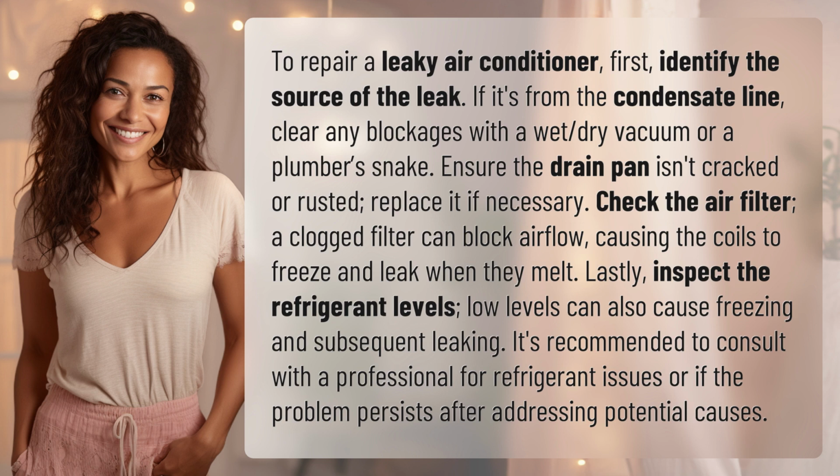A clogged filter can block airflow, causing the coils to freeze and leak when they melt. Lastly, inspect the refrigerant levels. Low levels can also cause freezing and subsequent leaking. It's recommended to consult with a professional for refrigerant issues or if the problem persists after addressing potential causes.